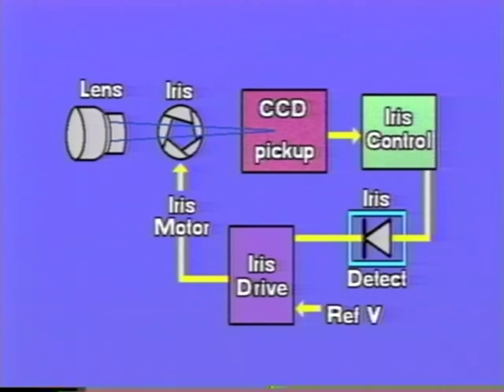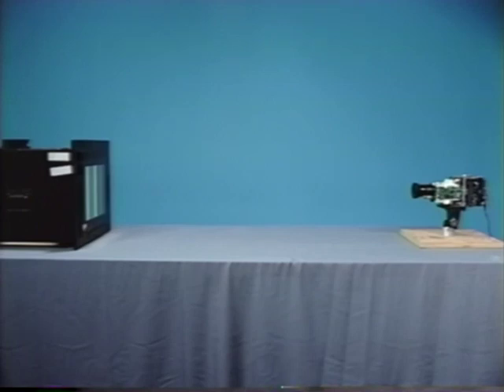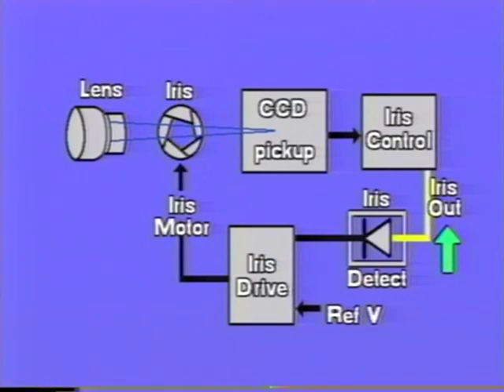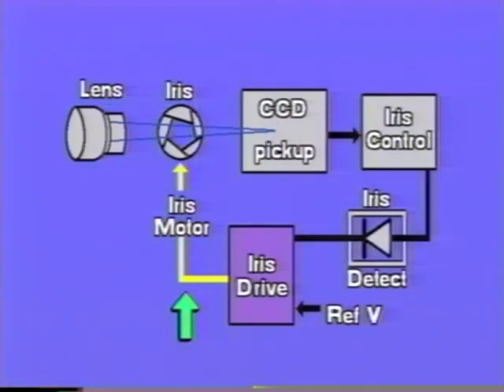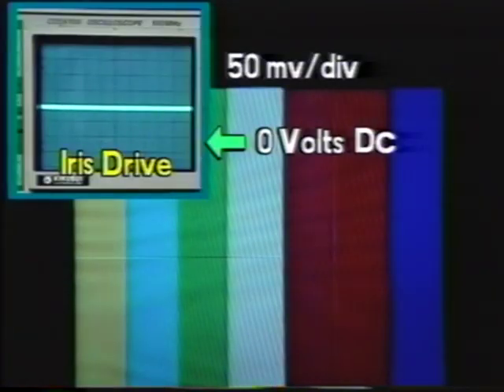To prove that the iris section works, we have placed a light box with a color bar pattern in front of the camera. As the light level of the light box is varied, observe the iris out signal on the scope. Notice that as the light level is raised, the iris out signal first increases in amplitude and then decreases back to normal as the motor operates to close the iris. As the light level is lowered, the video amplitude decreases, then increases back to normal as the motor operates to open the iris. You can also scope the iris driver output to verify iris drive operation.